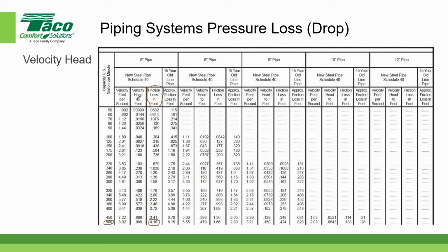However, the other two values would not change. In this case, the velocity in feet per second was for a 5-inch pipe, and the velocity head in this case was 0.999 feet. So the only thing that would change from one chart source to another would be the friction loss, and that would depend on how conservative the manufacturer was, or which equations the manufacturer or the person that created the chart used, because there are several methods for determining the friction loss in feet per 100 feet. Hopefully that answers the question.